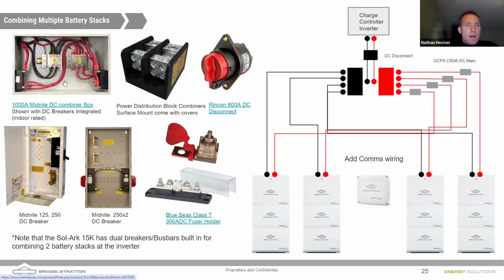What you see here is a combiner, but these are individual inputs. So single pole DC breakers on the positive cables coming in. And it looks like you've got 6 different inputs on this 1000 amp combiner. You can use power distribution blocks, but you will still need to provide overcurrent protection for your combiners. And so we're recommending overcurrent protection. Typically, we see 300 amp breakers. The maximum you can use on each stack could be a 350 on your combiner.